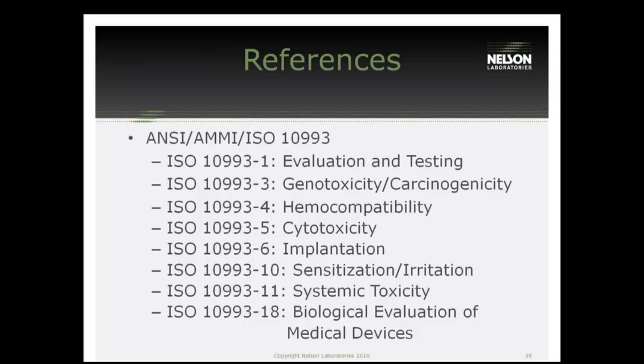The next question: which tests are common to ISO 10993 and USP Class 6? The big three — cytotoxicity, sensitization, and irritation — are the most common for ISO 10993. Systemic injection and material-mediated pyrogen are the next. USP Class 6 is a little different — the tests aren't identical to ISO, with different extraction fluids and things, but they're similar. Your intracutaneous reactivity is in the USP Class 6, and they add a systemic injection and an implantation — that's the USP Class 6 combination.